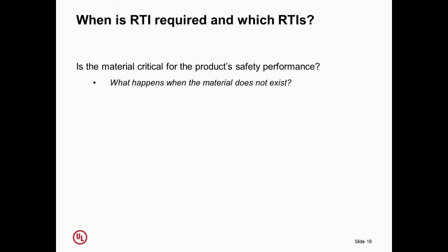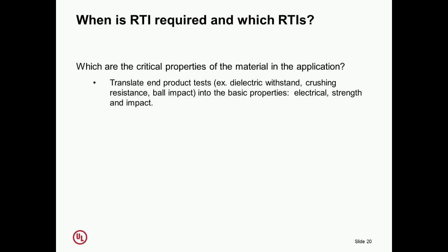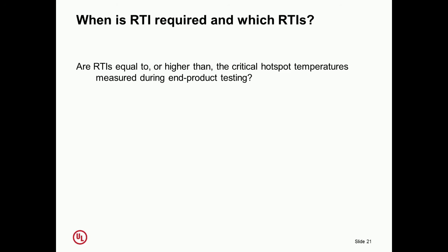When is an RTI or relative thermal index required and which RTIs are required? In the device where the polymeric is relied upon to comply with standard requirements, it would be necessary. What happens if the material doesn't exist? Will the product still perform? Will it still be safe? Will it still avoid hazards from shock or fire? Then what are the critical properties we'd want to look at to determine if it's suitable? We'd look at things like the dielectric withstand strength of that material, maybe the bulk resistance, perhaps mechanical strength such as crushing or ball impact. We'll be looking primarily at electrical strength and impact tests.